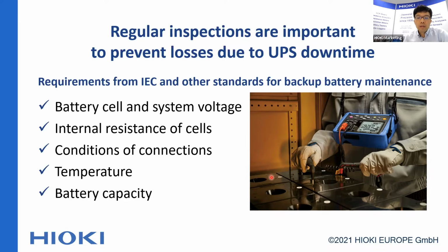According to the IEC standard for backup battery maintenance, these tests are required: battery cell and system voltage, the internal resistance of cells, and conditions of connections, temperature, and battery capacity. Doing this test, you can find degraded battery cells and change them to new ones to keep your UPS system healthy at all times.